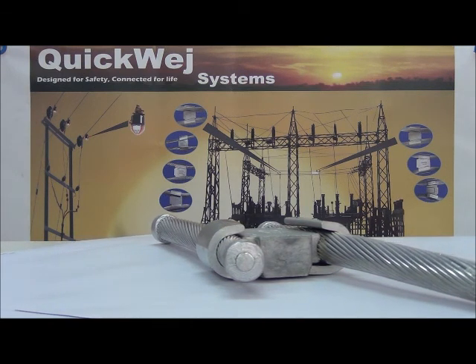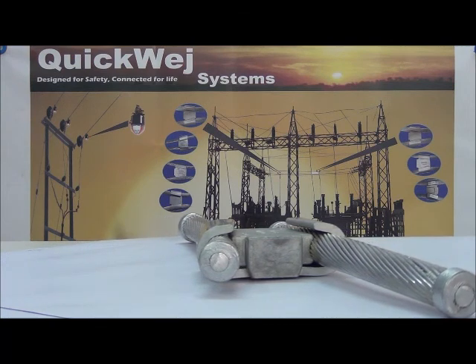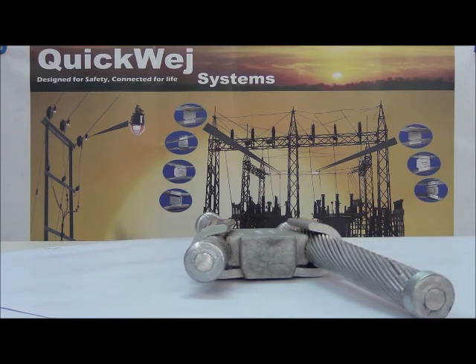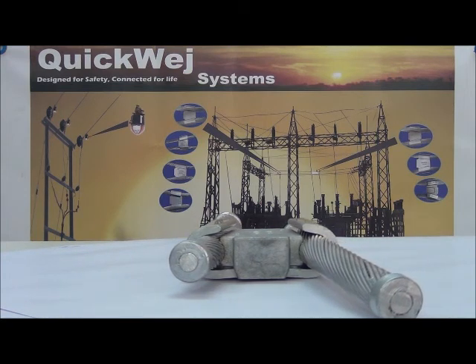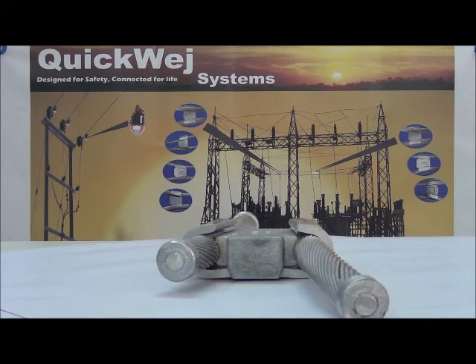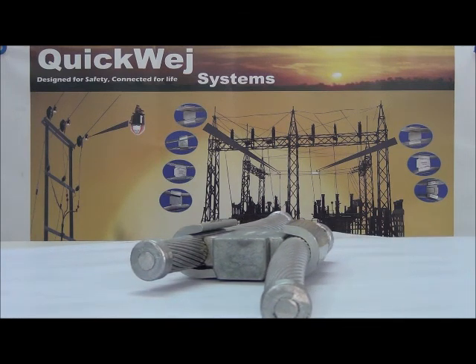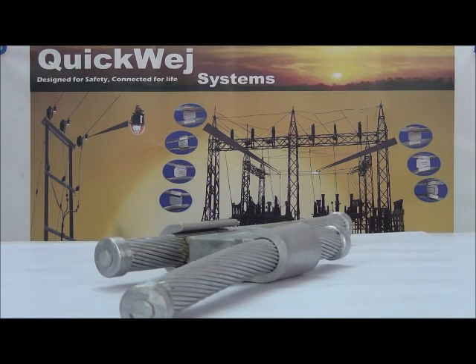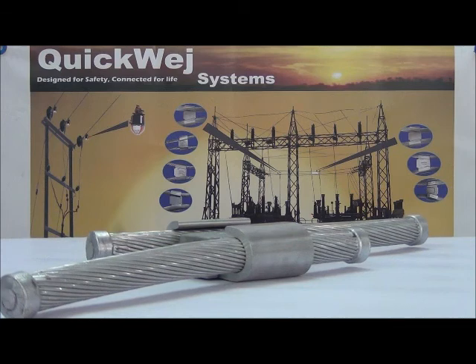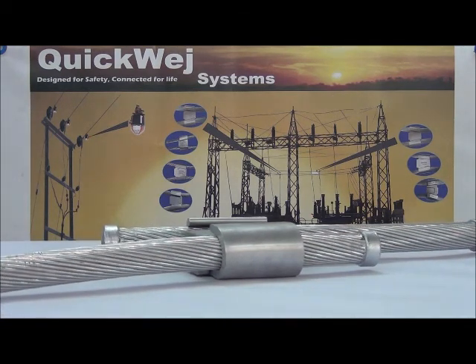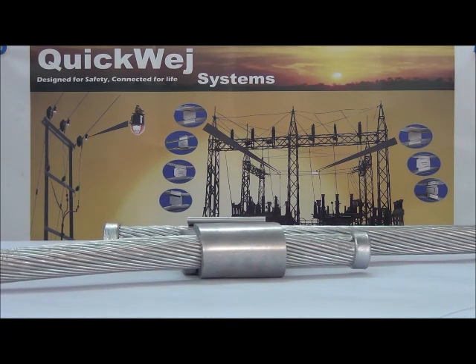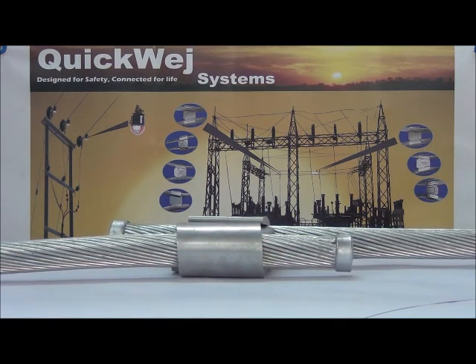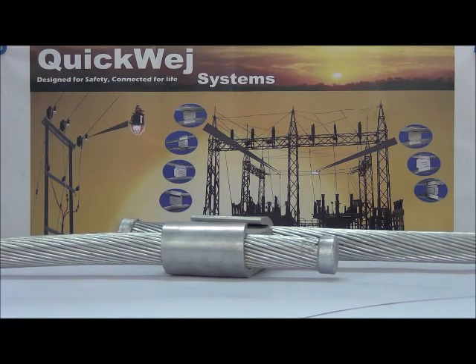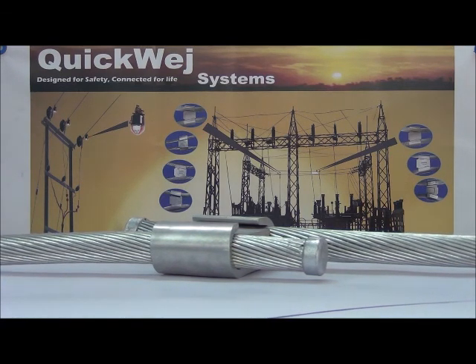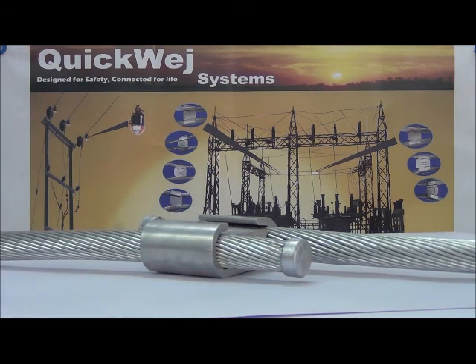Advantages of using QuickWej are many. QuickWej can harness electricity in a better way as compared to its bolted counterparts. The anti-corrosive conductive gel applied will contribute to enhance the efficiency of QuickWej. This is hydrophobic in nature, and this compound protects the connector from environmental factors. Fine copper particles that are suspended in this component fill the minute unseen gaps to ensure maximum efficiency. Due to the spring property of the connector, or the expansion property of the C member, the connector reliability is very high. This means that using QuickWej will help in reducing AT&C losses.